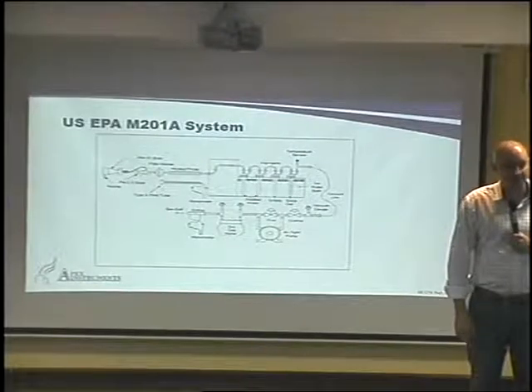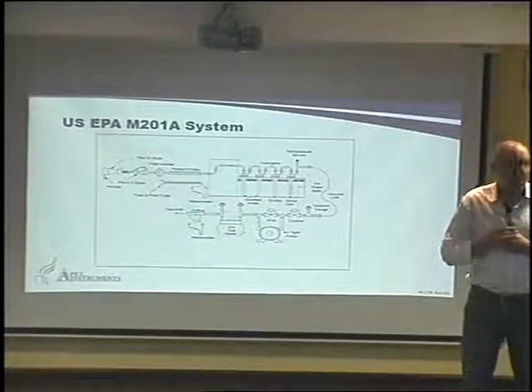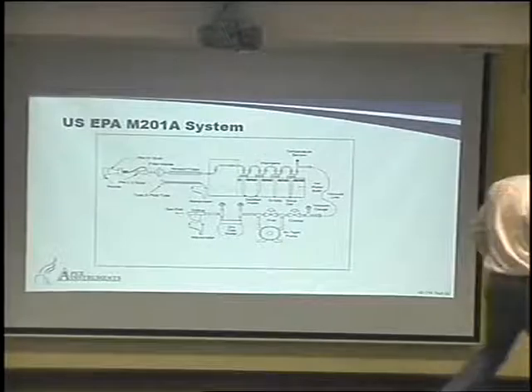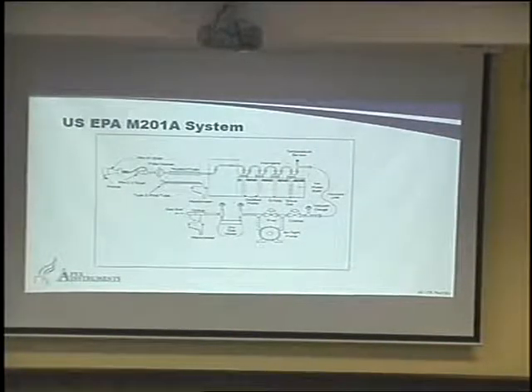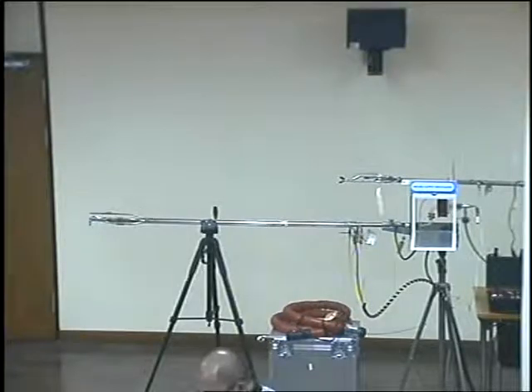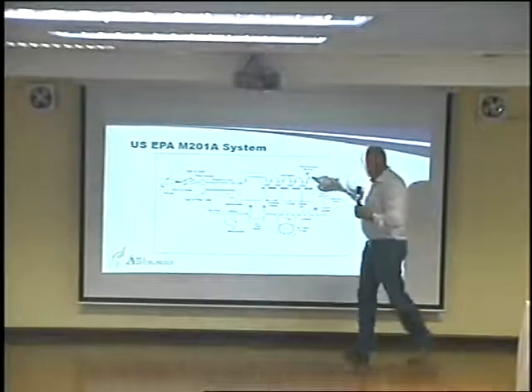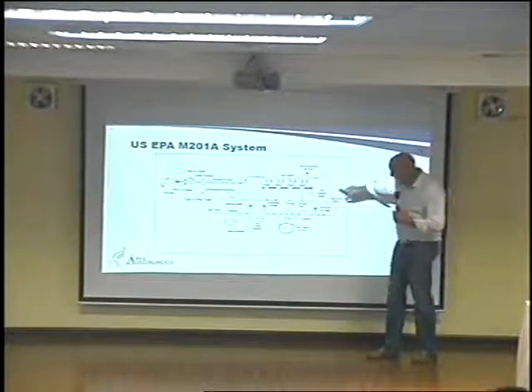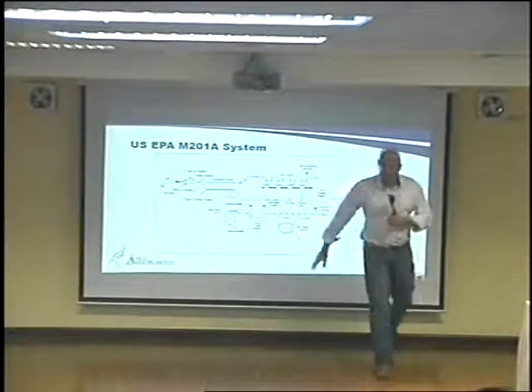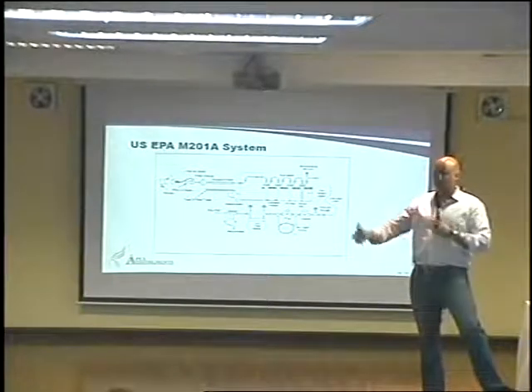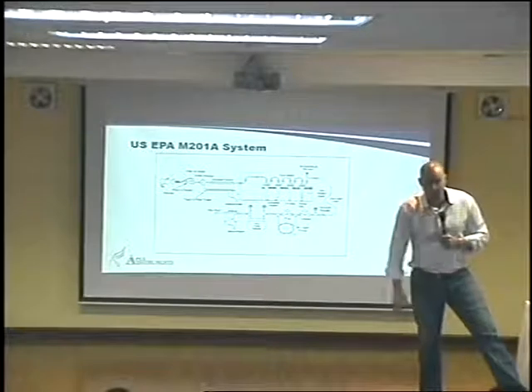So for a Method 201A sample, you would not have the Method 5 hot box, which is this guy right here. So this one here does not exist. And everything is at the front, okay? You come directly down the probe, and then the next stop is going to be your impinger bucket. So we have a part that mounts directly onto the impinger bucket. So it's a much smaller setup than Method 5 as well. Dry it up and things like that. You come out, that's your umbilical line, your sample line, and then all of this is included here in your console, whether it be a 502 or the 572 or whatever console that you're using, exactly the same as your Method 5.